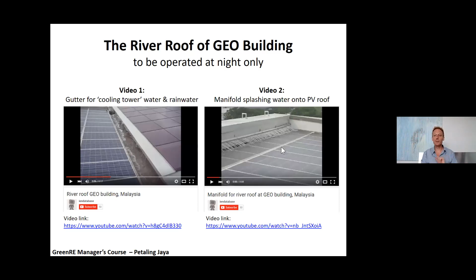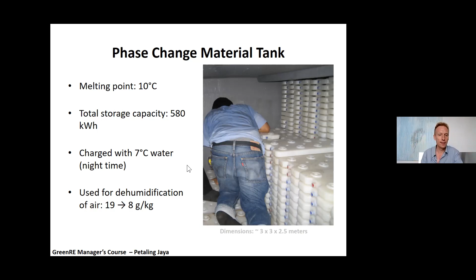The phase change material tank looks like this. It's basically a bunch of plastic packs, and inside there's a special salt solution that freezes at 10 degrees. To charge this, you need at least 7-degree water, a bit below, otherwise it won't freeze. This means we can just use a normal chiller. Then once we have this tank, in the daytime we run the water through, and the ice packs start to melt, giving off all this cooling, absorbing the heat from the water. So it's a smart way to store cooling.